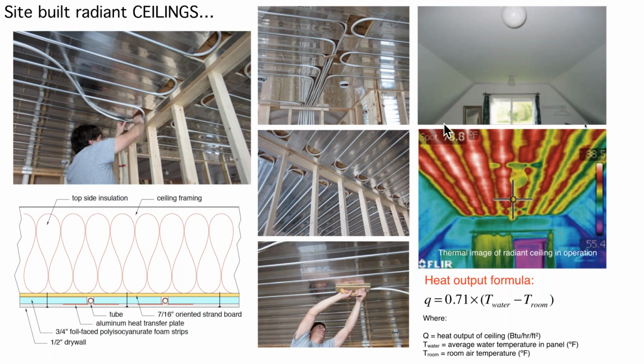And I can tell you, this room is 14 feet wide, and the ceiling is only 6 feet wide. And that ceiling can easily heat that room. And down here is an infrared thermal image of that ceiling. The red strips that you're looking at here show how that heat is being spread out by those aluminum plates. And you can actually see the water is flowing from left to right here because these plates haven't warmed up quite as much over here. But this is really good. This shows you it is critically important to have those aluminum plates in there.